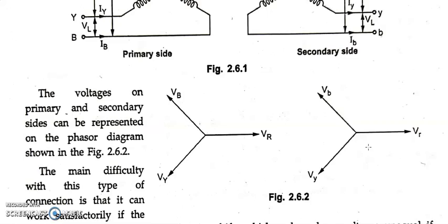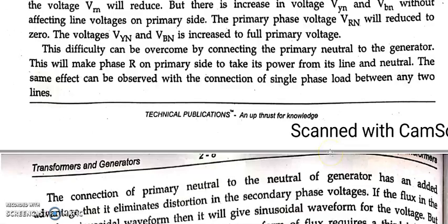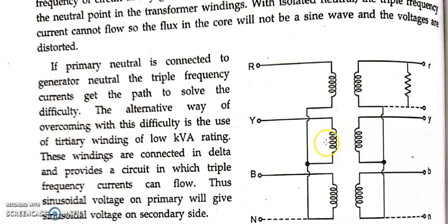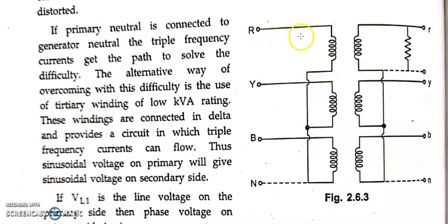Let's see how the connections are made. If using a bank of 3 single phase transformers, all the ends of one of the terminals of all 3 phases are shorted together, calling it neutral, and the remaining ends are given the supply R, Y, B. Similarly, on the secondary side, one end is shorted and called N, while the remaining terminals are called R, Y, B.